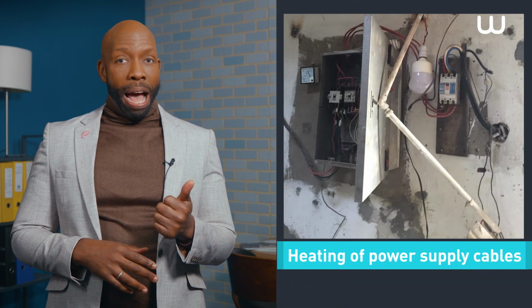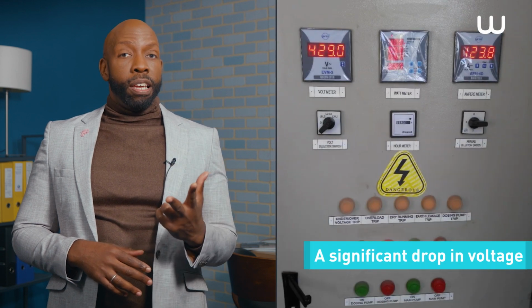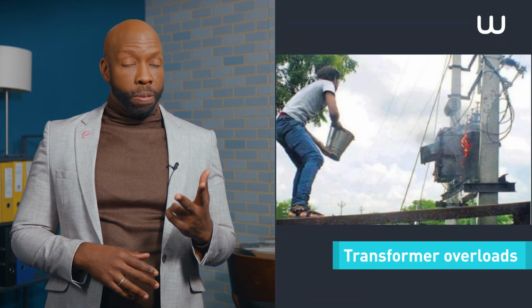Now, due to the significant amount of power required to supply sites connected in medium to high voltage modes, the circulation of reactive power in electricity supply networks causes various problems and potential risks, such as significant heating of power cables, a significant drop in voltage, transformer overloads.